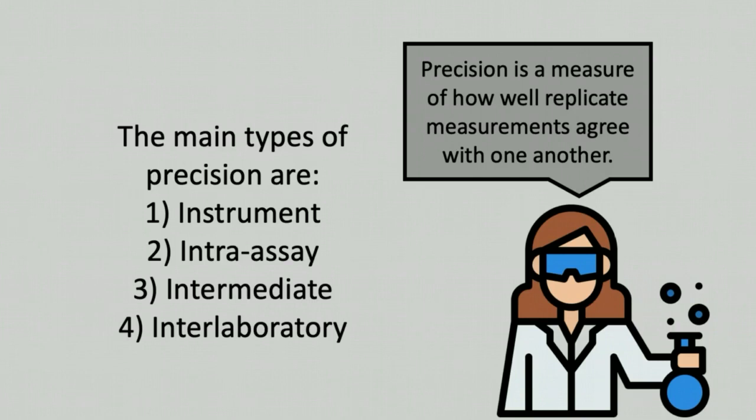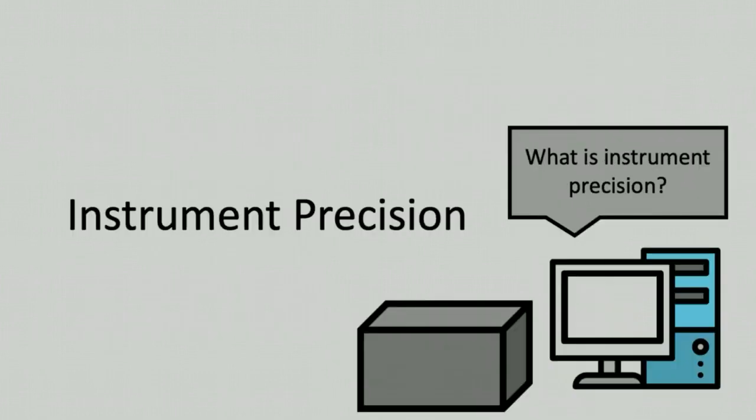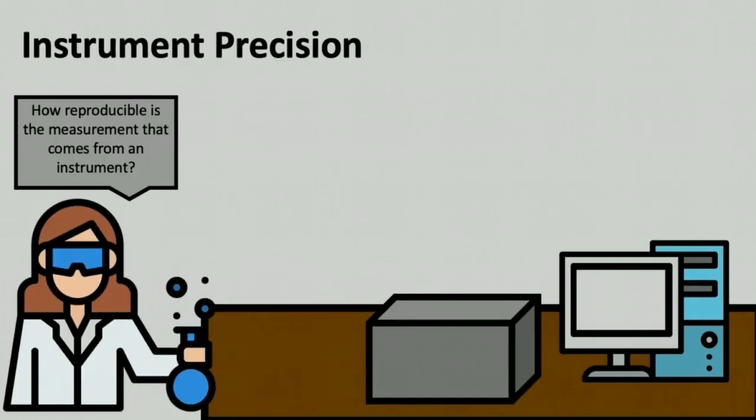The four types are: instrument precision, intraassay precision, intermediate precision, and interlaboratory precision. First, we'll look at instrument precision. Instrument precision is trying to answer the question: how reproducible is the measurement that comes from an instrument?